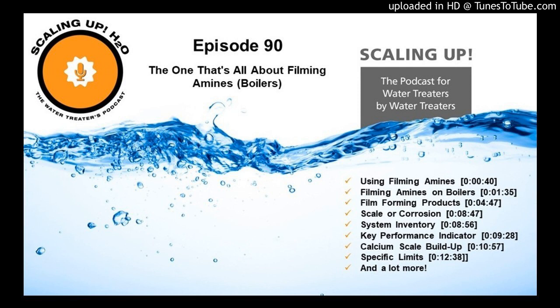It's got filming amines in it as some of the material, but then there's also other materials in there, whether that's an alkalizing amine or an application specific compound. Okay. And so in the world of boilers, our cocktails are generally derived of filming amines and alkalizing amines of some combo. Pick your favorite filmers, pick your favorite alkalizers.